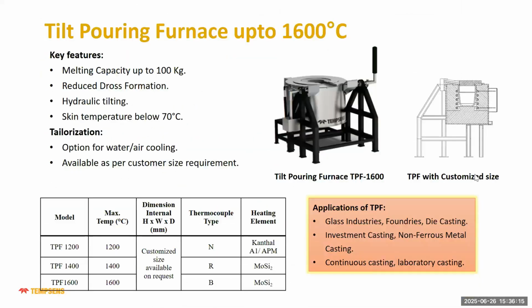Now the tilt pouring furnace. Tilt pouring furnaces are used in glass industries, foundries and die casting. The material will be heat treated inside this furnace, and there will be a tilt mechanism. Hydraulic tilting or manual tilting, depending on the weight of the furnace, can be done. We can melt up to 100 kg of material, and hydraulic tilting can also be done. We can use different temperatures and different heating elements for different applications: 1200 degrees centigrade, 1400 degrees centigrade, and 1600 degrees centigrade.